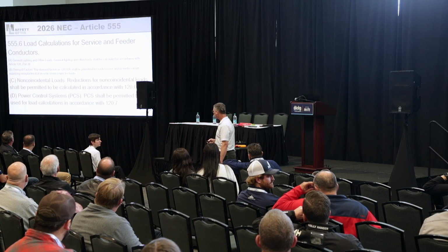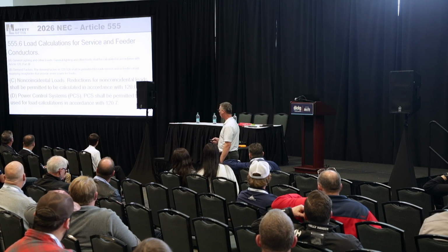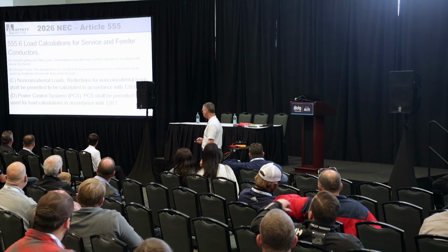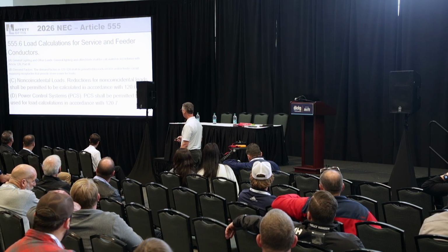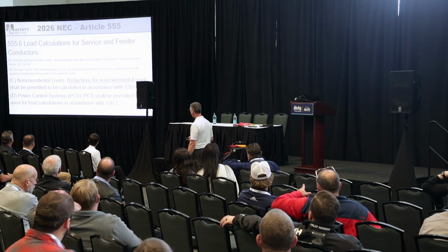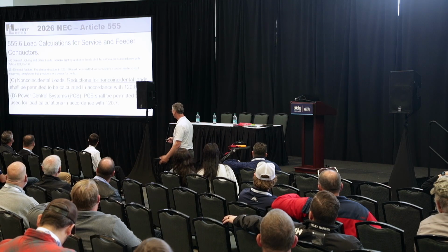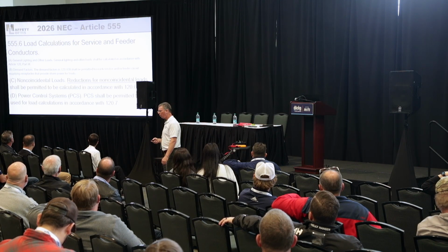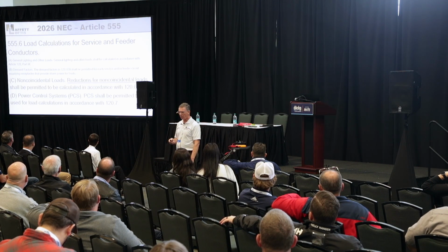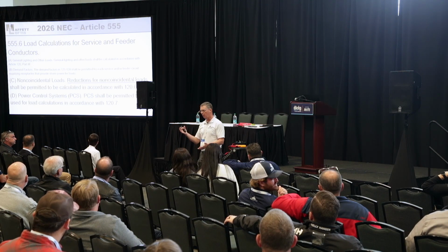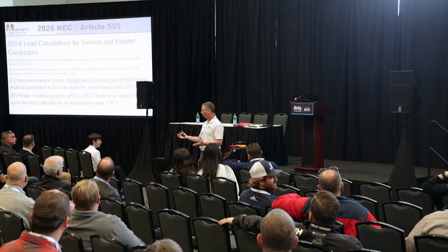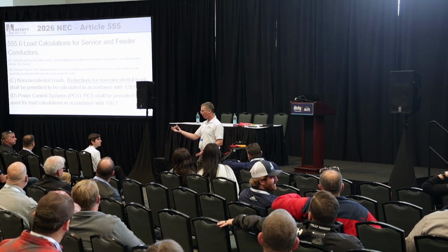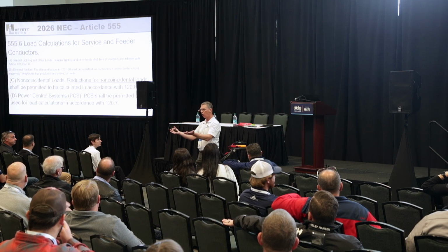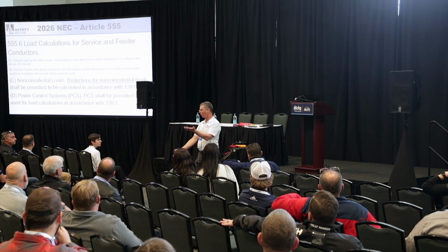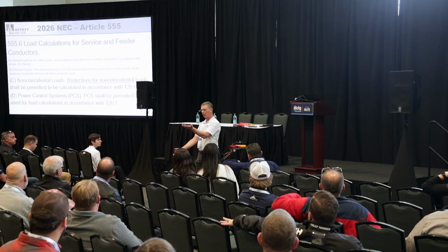Load calculations, and moving on to other codes that have been changed in 2026. We're talking about reduction of non-coincidental loads. The code making panel realized that there could be some loads that only run at a certain time, say there are 2 loads out there but only one runs at a time. We only load for the heaviest load.